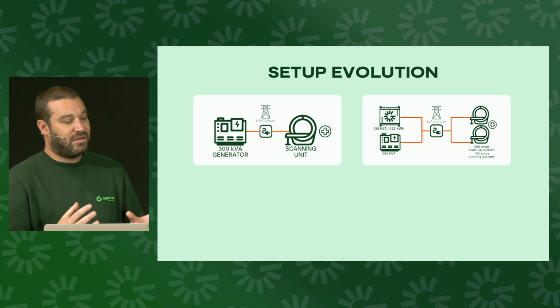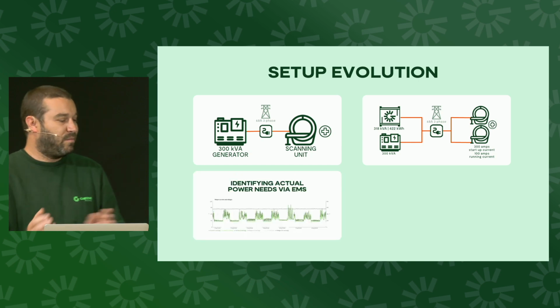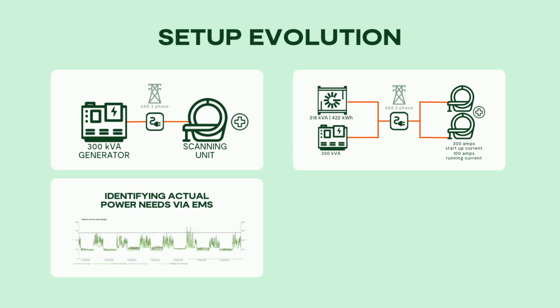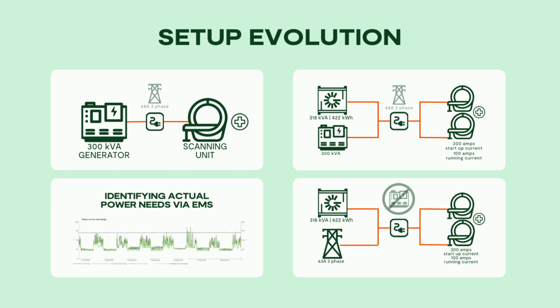So they had sufficient power available to drive the scanners, but also through the installation of the battery, we start collecting data. All that data is being pushed up to the cloud and then displayed in Greener projects, as Robin was saying. So you can see the example load profile there. We'll go into a bit more detail on that shortly. But through this data, we were able to understand that the 63 amp 3-phase power supply was actually sufficient to provide the energy required to run both scanners.